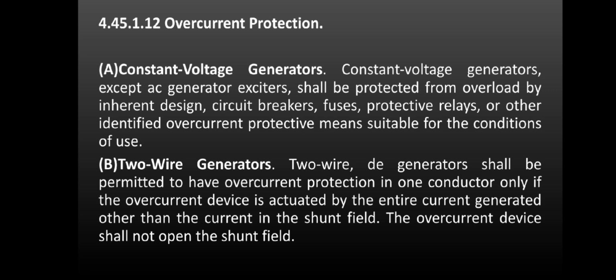Constant voltage generators, except AC generator exciters, shall be protected from overload by inherent design, circuit breakers, fuses, protective relays, and other identified overcurrent protective means suitable for the condition of use. Two-wire generators. Two-wire generators shall be permitted to have overcurrent protectors in one conductor only if the overcurrent device is actuated by the entire current generated, other than the current in the shunt field. The overcurrent device shall not open the shunt field.